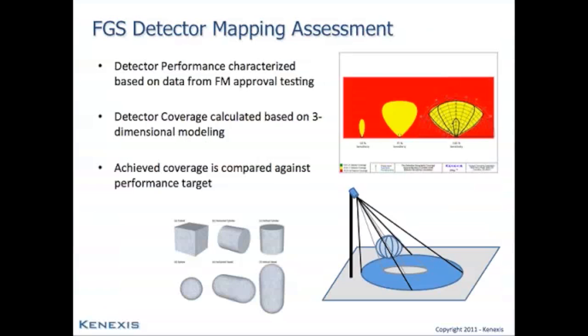When performing a fire and gas detector mapping assessment, one needs to consider many attributes of the zone in consideration. The first consideration would be the performance of the detector. The performance of the detector is generally calculated, determined, and measured by the equipment vendors that are providing the detectors. In the picture to the right, you can see that an optical fire detector vendor provided what is called a cone of vision drawing for their detector at 3 different sensitivity settings: high, medium, and low.